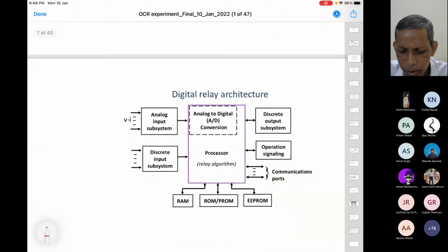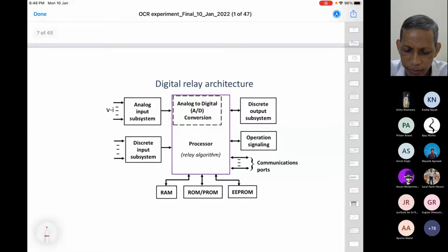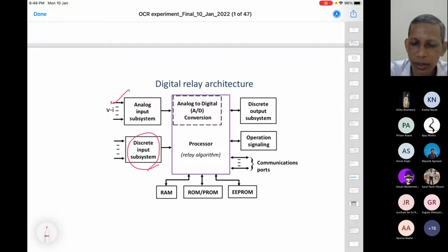So the way I am talking about the numerical or digital relay: we have current and voltage inputs. Also, you can have a discrete input, like a command from another, adjacent relay, saying remain silent, don't trip, this is my job, not yours. Agree? Or from the remote relays also, the corresponding current information can come into the system. So this is just like any digital device.